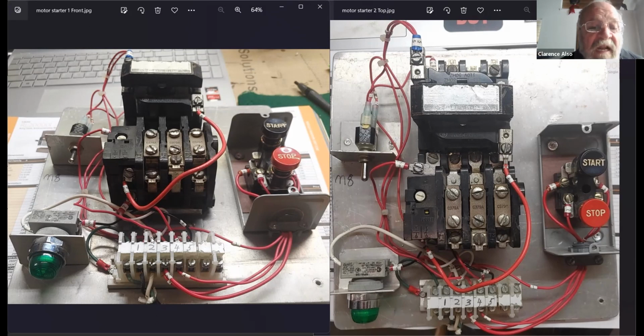Remember, on the 6 side of the coil, we had a set of contacts. That's on the 0 side of the coil, the 0 volt side of the coil. It went to neutral, and then from neutral it went to a set of overload contacts. And then from that point, if it wasn't overloaded, then the neutral is felt at terminal number 6. They're on the overload, and then it goes up there to the coil.